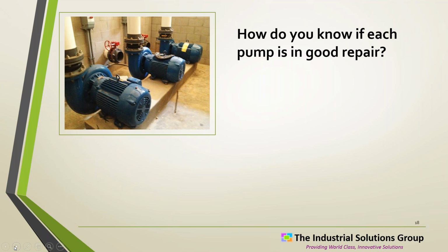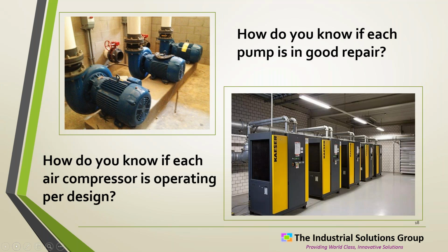So here's a question. That's a pretty nice 3-pump set. Good installation, good foundation, it's clean. But how do you know that those pumps are actually in good repair? It's not obvious. We aren't showing a lot of pipe, but pressure gauges, how do you know? How do you know what's going on with these pumps? How do you know what's going on with these air compressors? You'd think they look good, but I've seen compressors like that, and one of those compressors just won't work. Can't even get it to run. So how do you know? How do you know if you're operating well, if you're operating per design? How do you know if you're going to have a problem?